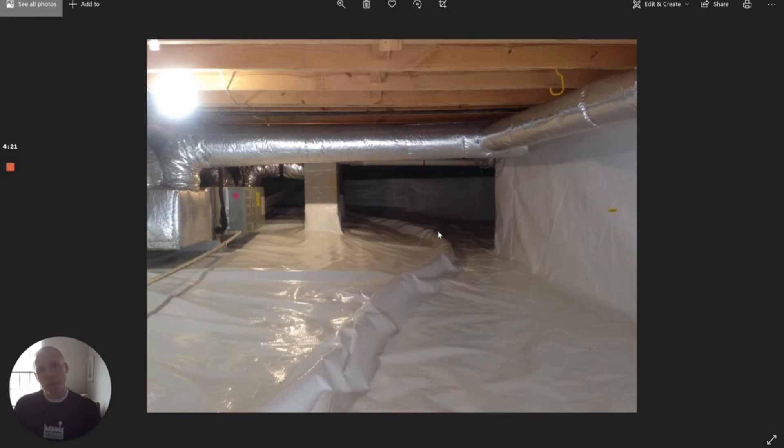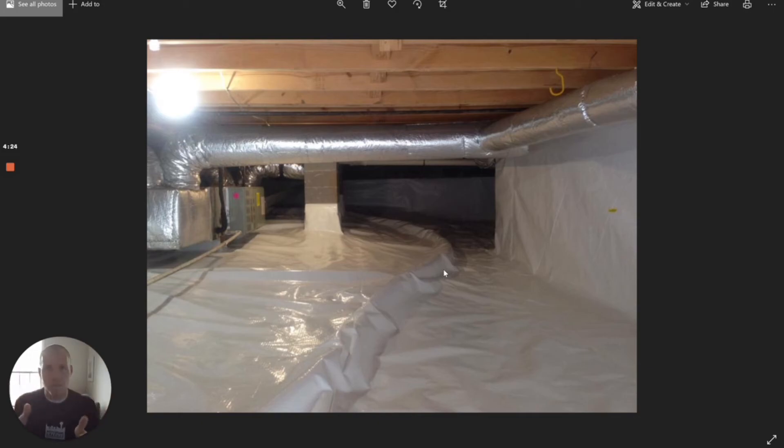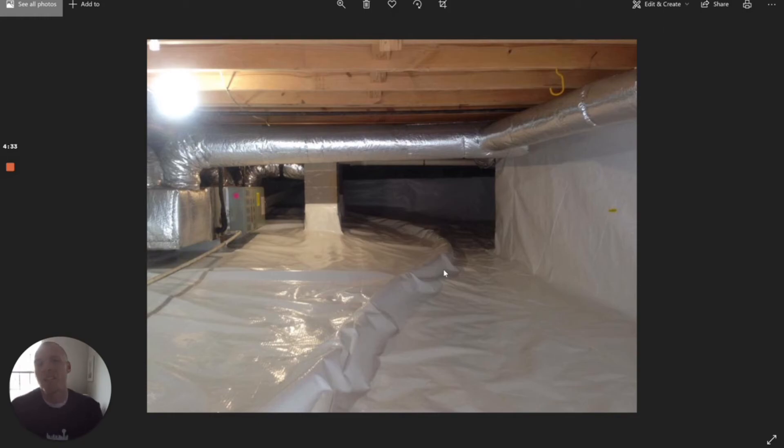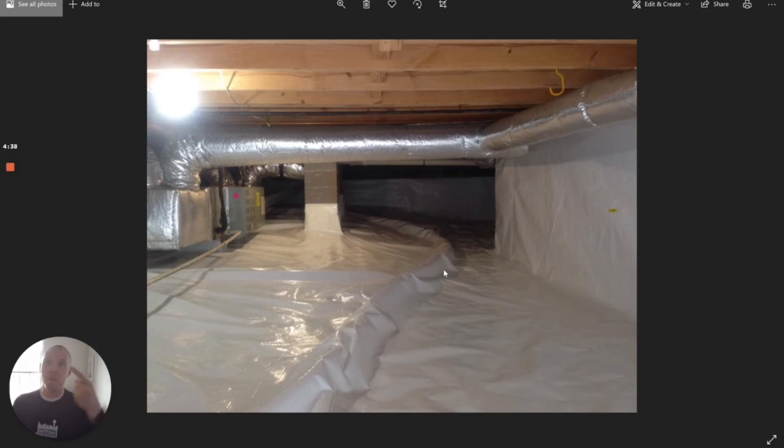And notice that the vapor barrier is wrapped around that pipe. It's actually with suction—it's created suction to pull that plastic down around the pipe. That's showing us that the pipe running underneath the vapor barrier and the fact that the vapor barrier is all sealed creates suction. So now we're pulling from underneath the plastic.